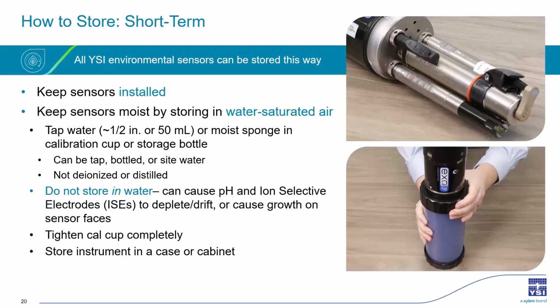This can be tap water, bottled water, or even site water in a pinch. But if you do end up using site water, go ahead and change it out for tap water as soon as you can. And you don't want to use DI or distilled water for this, and you don't want to submerge the sensor in the water because it can shorten the lifespan. This is especially important for pH or ISEs like ammonium, chloride, and nitrate because it can deplete the reference solution and potentially cause them to drift.